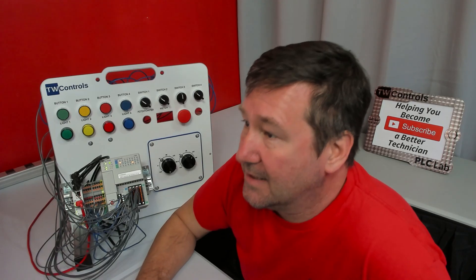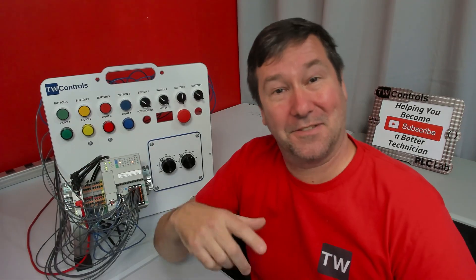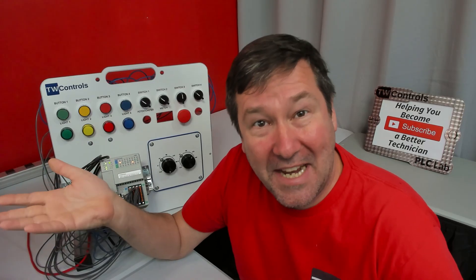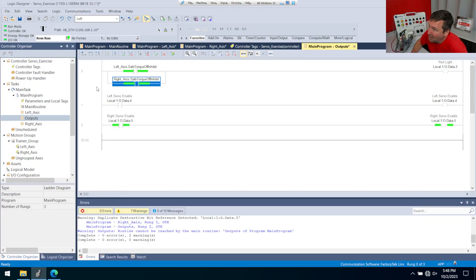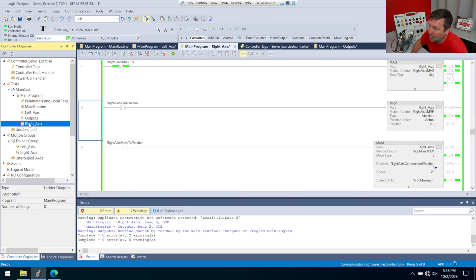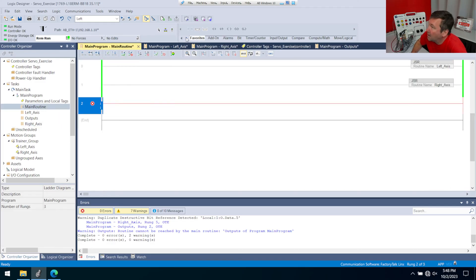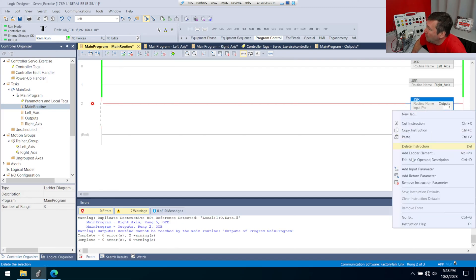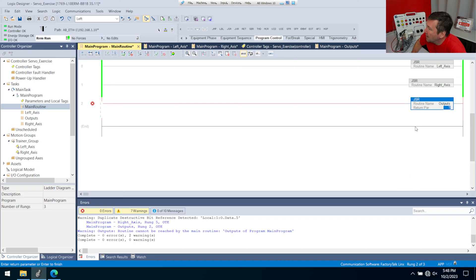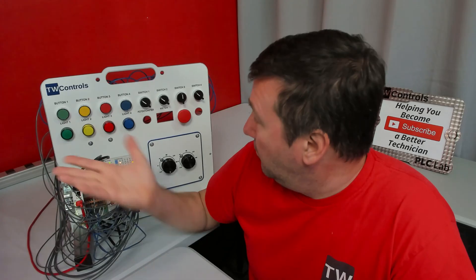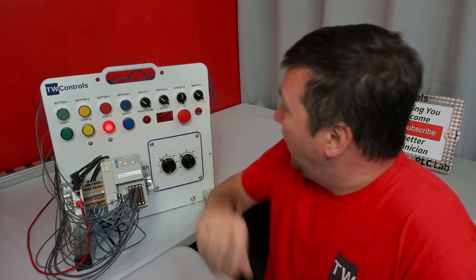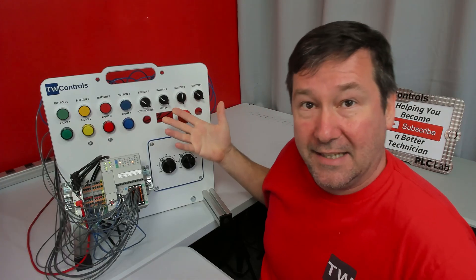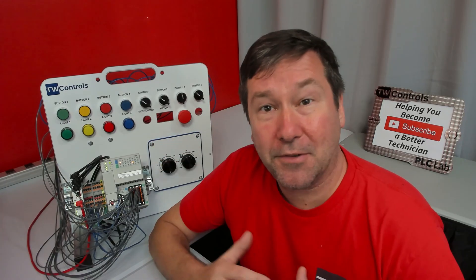Our red light does not come on yet because we added that output routine but didn't make a JSR to call it. This is why I always drill into technicians to pay attention to the green bars on the left and right side — they don't seem important until they're not there. Go to the program control category, find our outputs routine, add a JSR and remove the unused parameters, then finalize. When we do, our red light comes on. Pull out the red mushroom button and that clears our safe torque off issue.